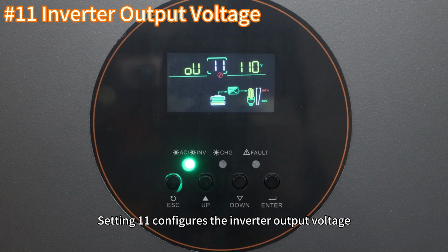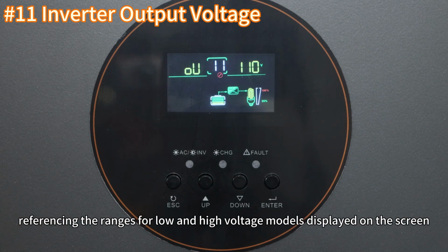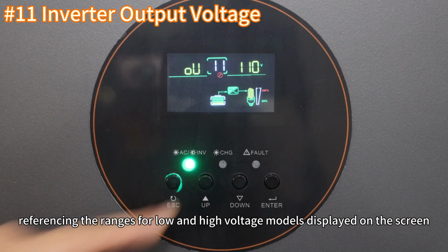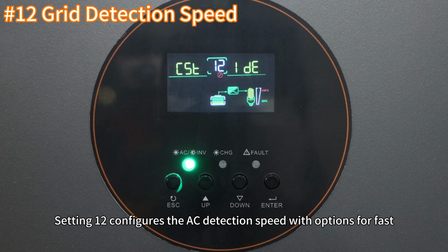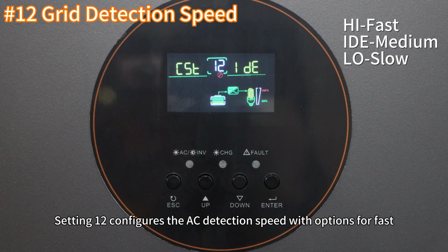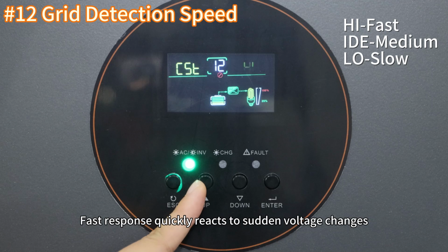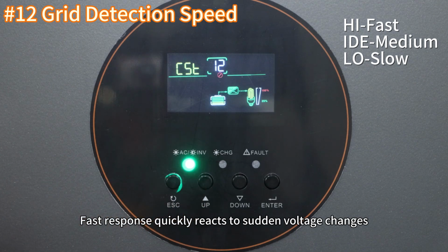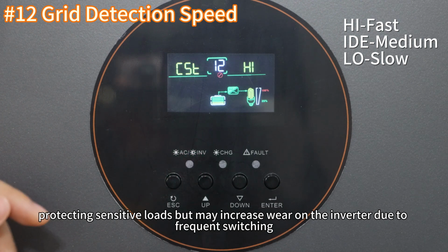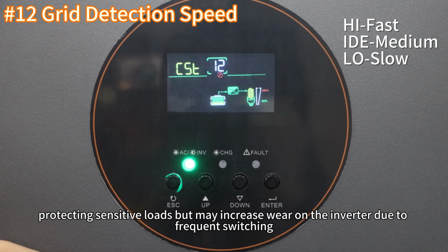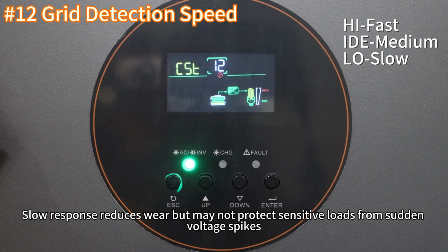Setting 11 configures the inverter output voltage, referencing the ranges for low and high voltage models displayed on the screen. Setting 12 configures the AC detection speed with options for fast, medium, and slow. Faster response quickly reacts to sudden voltage changes, protecting sensitive loads but may increase wear on the inverter due to frequent switching. Slow response reduces wear but may not protect sensitive loads from sudden voltage spikes.